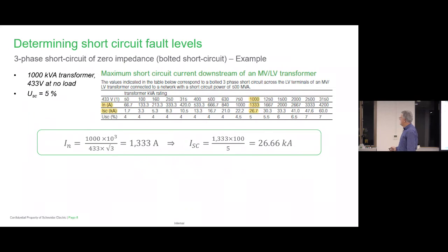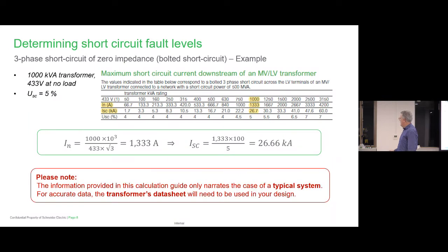And this is the key point here. This is the impedance value of the transformer. That's what you need to know. And you can see it's here in part of the formula. But what we're saying is you need to get this information from the transformer manufacturer and get that data from him. That's your starting point.